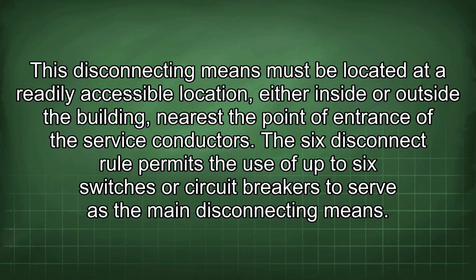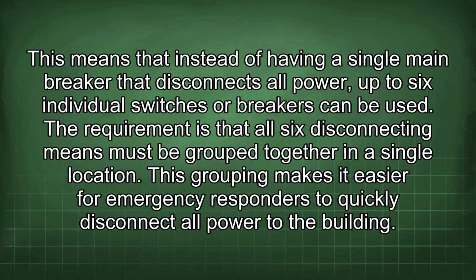The 6 disconnect rule permits the use of up to 6 switches or circuit breakers to serve as the main disconnecting means. This means that instead of having a single main breaker that disconnects all power, up to 6 individual switches or breakers can be used. The requirement is that all 6 disconnecting means must be grouped together in a single location. This grouping makes it easier for emergency responders to quickly disconnect all power to the building.